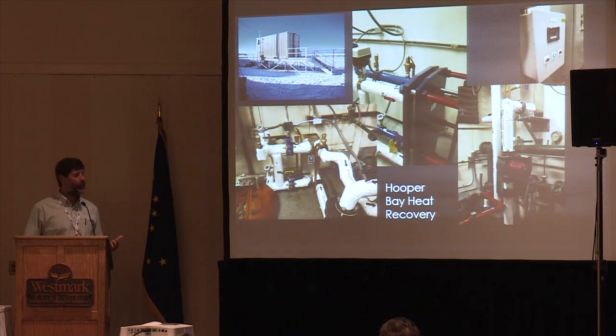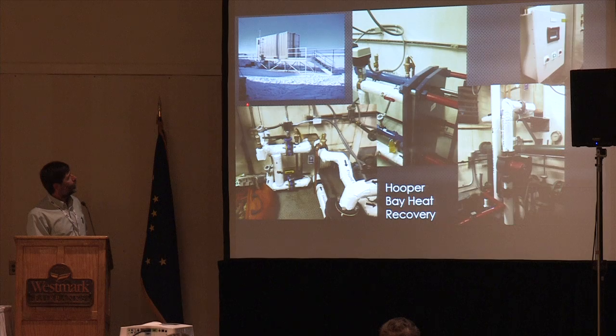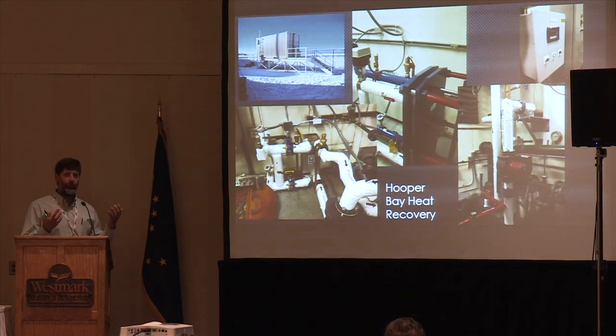So they want to put in a heat recovery system. We've got to have individual heat exchangers for each one of those cooling systems that's drawing heat, and it goes into a centralized box. They run their water system through that box, and with that plate and frame heat exchanger, we're exchanging temperatures, raising their water temperature and benefiting the city.